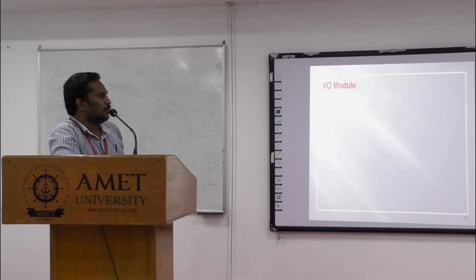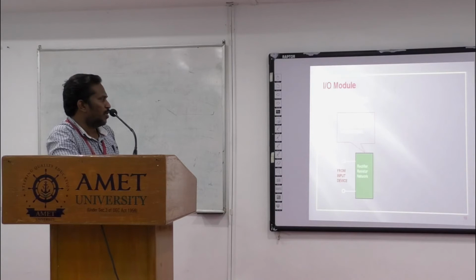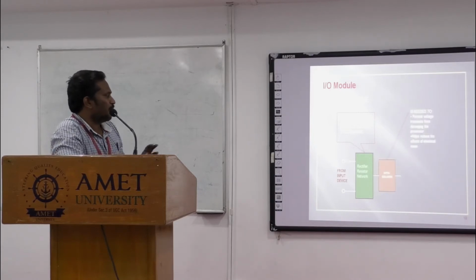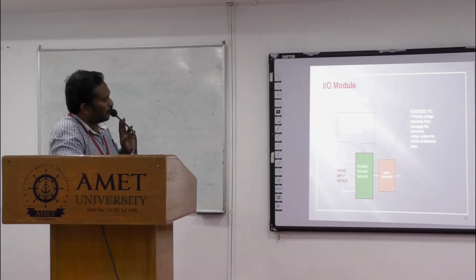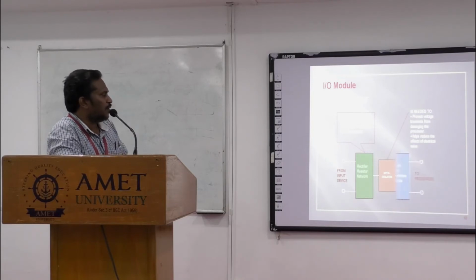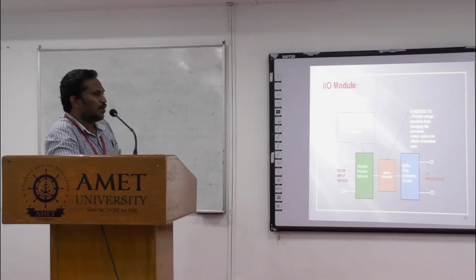AC input module. If the field input device is DC, you have to go for a DC input module. If the field input device is AC, then you have to go for an AC input module. In the AC input module, there will be a rectifier unit because your CPU input is DC voltage, so we have to convert AC into DC. From the input device, the AC voltage will be converted into DC in the rectifier unit. That will be sent to the opto isolator. The opto isolator will convert it into usable DC voltage that will be fed to the CPU unit.